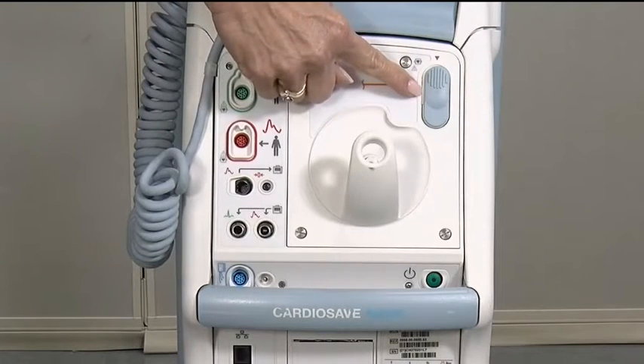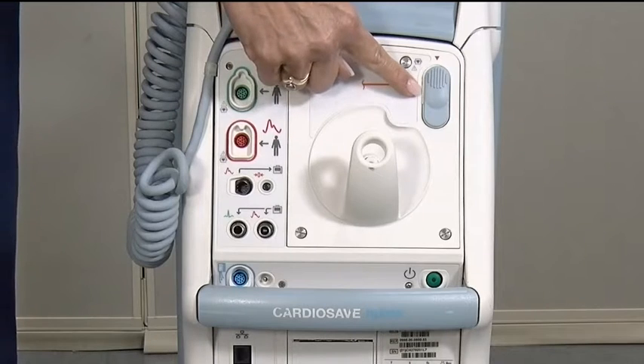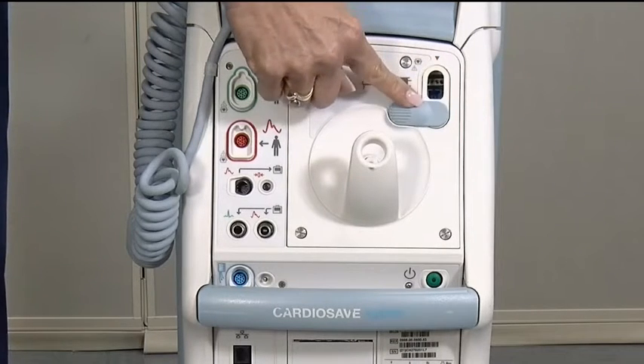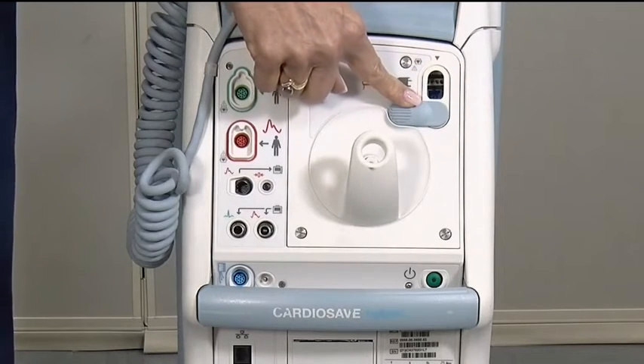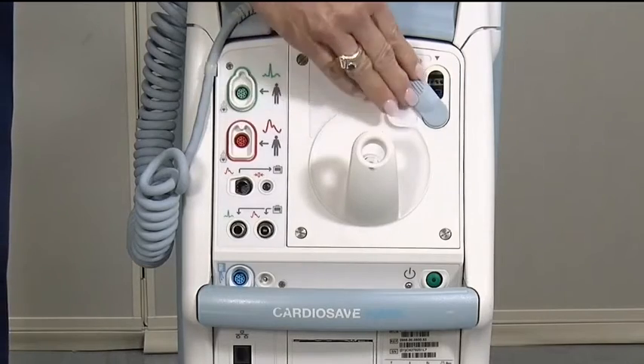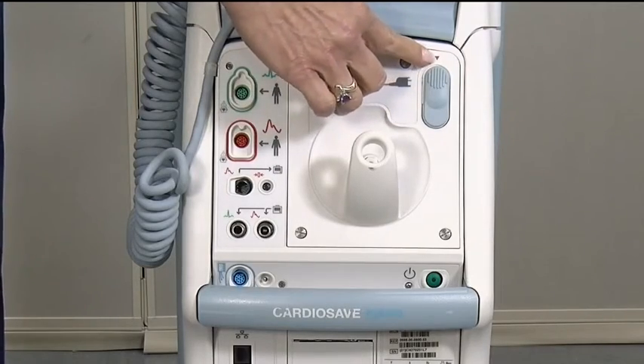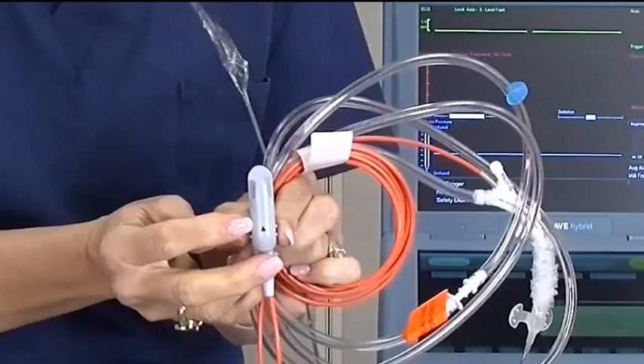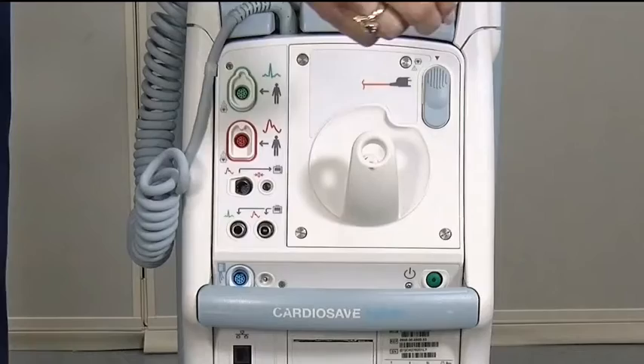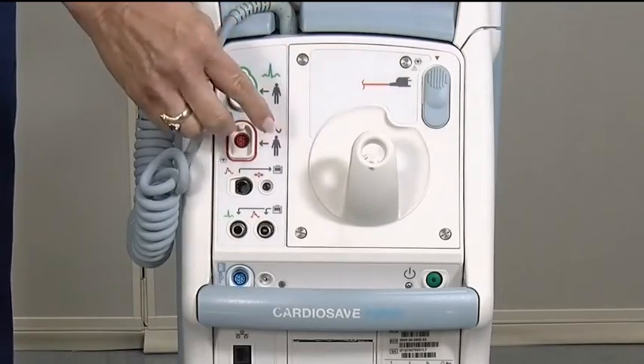This little trap door here is where we put our fiber optic catheter. You open the trap door and you put the fiber optic sensor connector into the port. There's a little red triangle at the top, and there's also a red triangle on the catheter sensor connector. You want to match those up and slide it in.